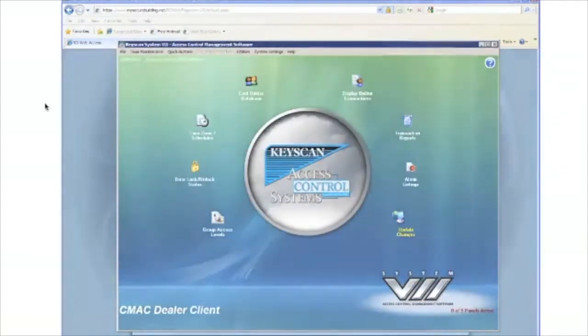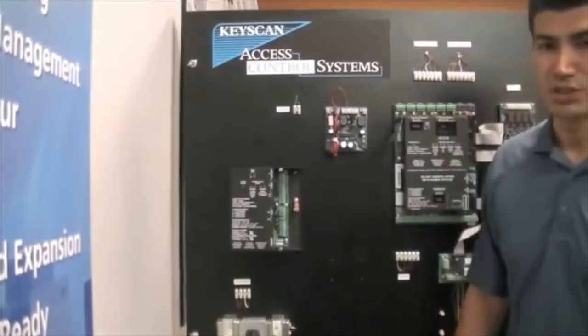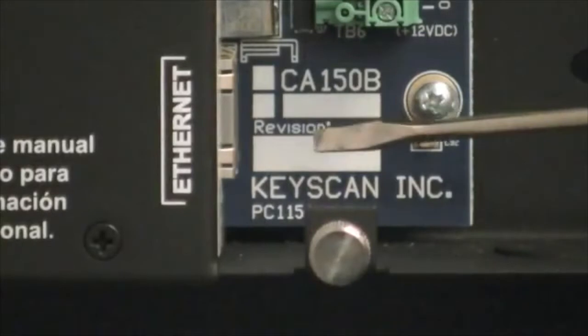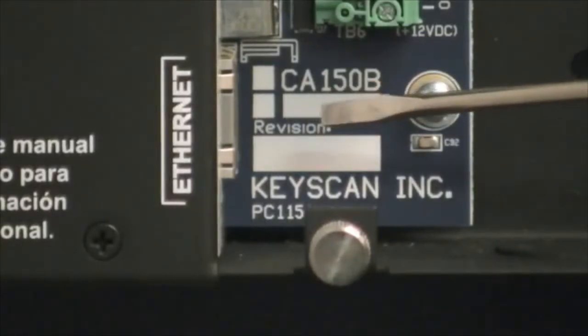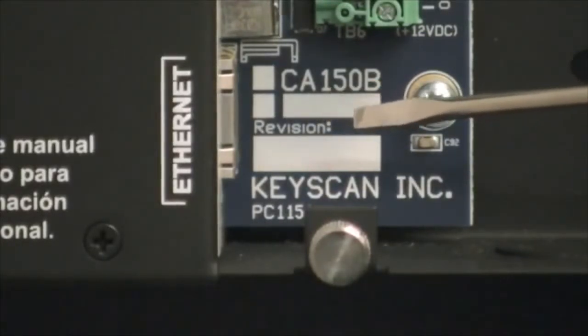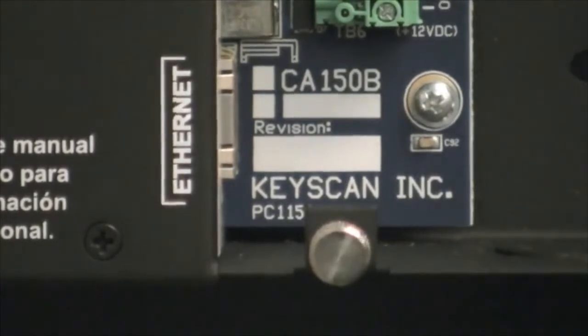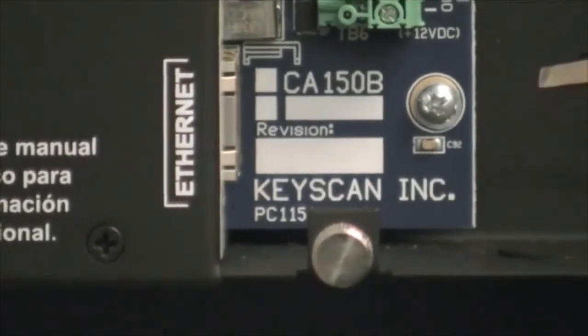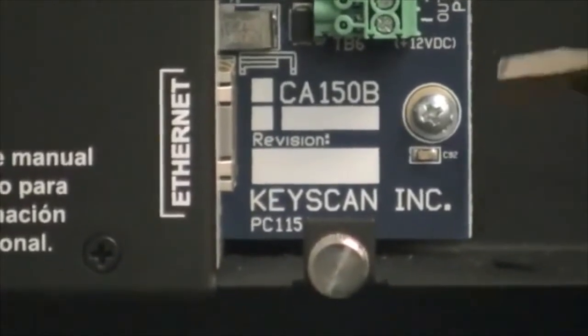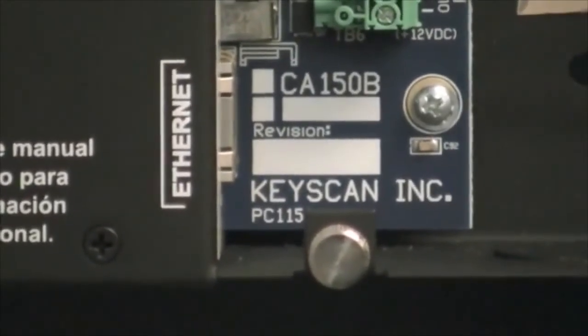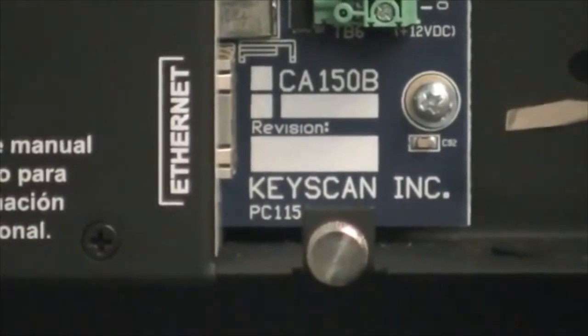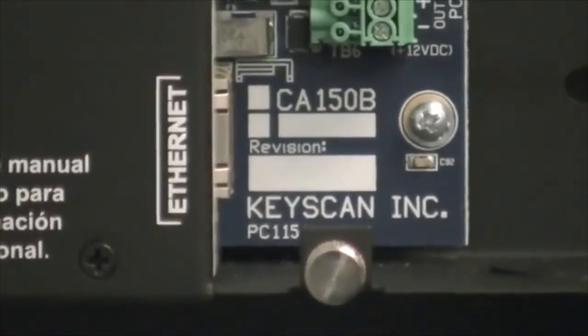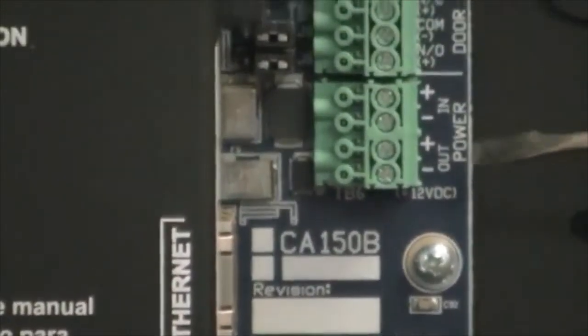Let's now review the connections of the CA-150 single door access control unit. This is our PoE Ethernet connection for the CA-150. The PoE connection provides power to the CA-150 unit and all of the devices for the door that are connected to the CA-150. There's approximately 680 milliamps total current available for these devices.